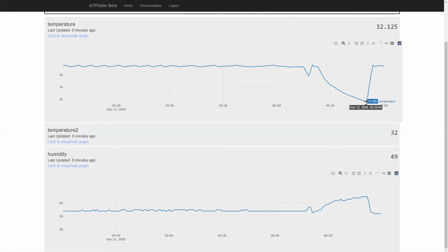Whereas here we have turned on the incubator. This is pretty much a straight line. We don't see this type of two slopes or different rates here. The reason is that the incandescent bulb gives out a constant heat depending on the wattage of the bulb. Since the heat delivered is constant and the temperature difference does not matter much, we see a fairly straight line here for the heat increase, at which point the temperature went above the threshold. So the controller held the temperature constant at 37.5. So that's the reason why we see this graph.